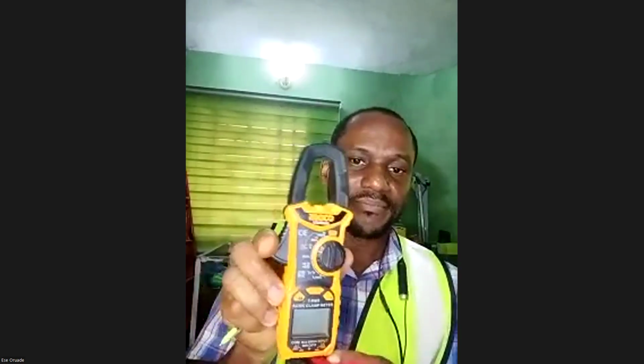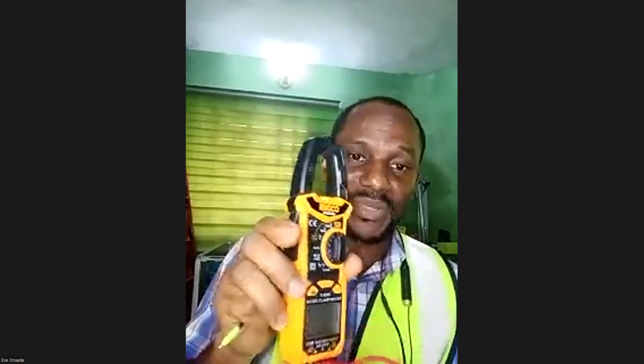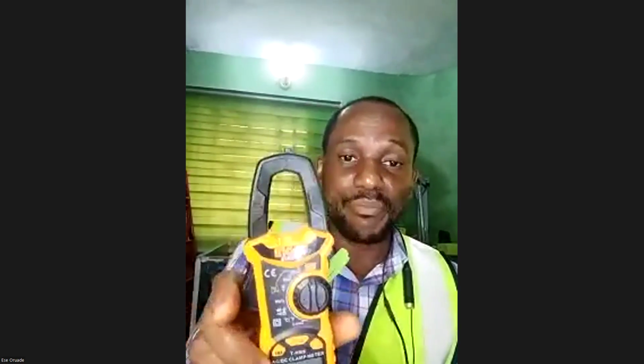You latch it this way. Another beauty of this clamp meter is you can use it to measure current of a live circuit, one that is energized. For instance, your inverter is running and you want to compare the current it indicates on its HMI with the actual value from your meter. You just get one of the live cables, open the clamp, and connect it around it.